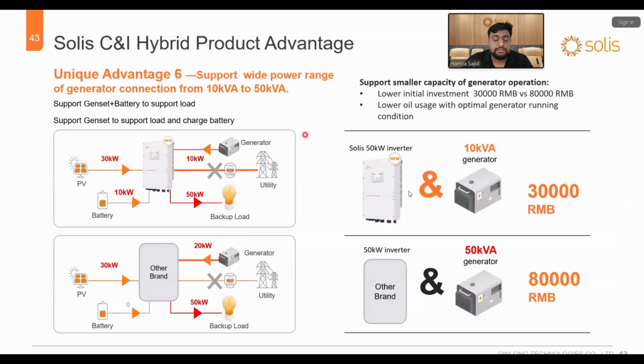The best feature for this is we do not bind the customer to a particular generator size, because our inverter can work together with the batteries and the PV at the same time with the help of a generator. Let's suppose the customer has a generator of 10 kilowatt, and the load running is 50 kilowatt. Our PV somehow is not available fully, so 30 kilowatt of PV is available. So if you have a 10 kilowatt generator, you can connect it to the gen port and it can support together with PV and the battery to support the load of 50 kilowatt.